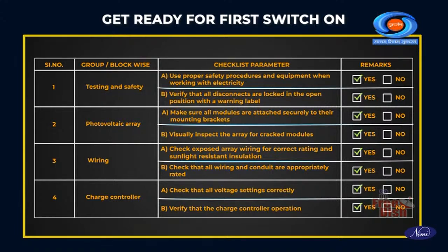Testing and safety. Checklist parameter. Use proper safety procedures and equipment when working with electricity. Remarks. Yes. Verify that all disconnects are locked in the open position with a warning label. Group or blockwise. Photovoltaic array. Checklist parameter. Make sure all modules are attached securely to their mounting brackets. Remarks. Yes. Visually inspect the array for cracked modules.